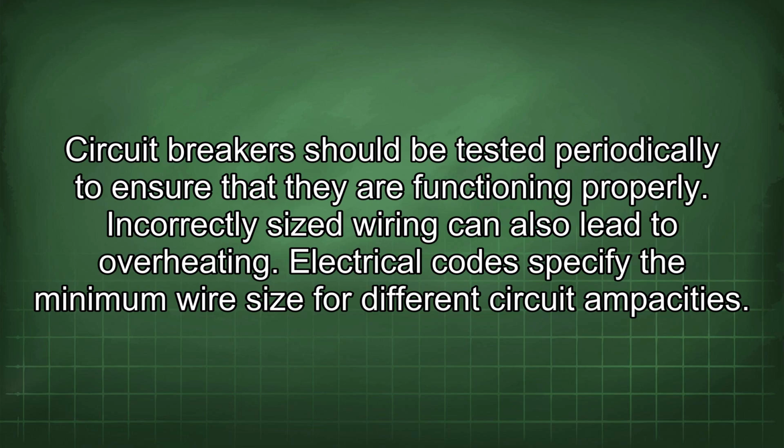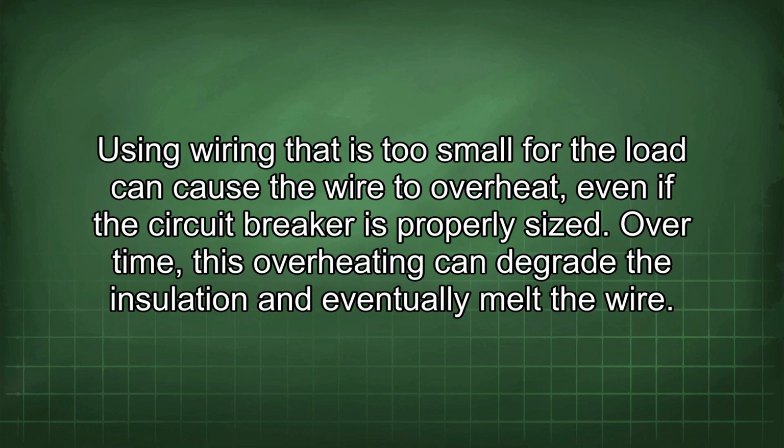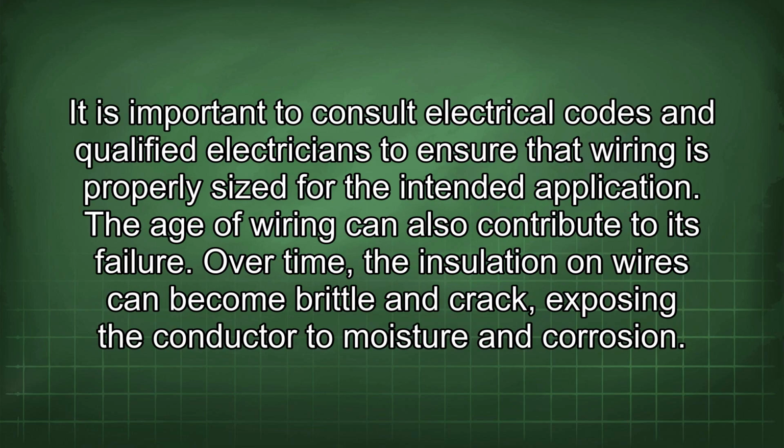Incorrectly sized wiring can also lead to overheating. Electrical codes specify the minimum wire size for different circuit ampacities. Using wiring that is too small for the load can cause the wire to overheat, even if the circuit breaker is properly sized. Over time, this overheating can degrade the insulation and eventually melt the wire.